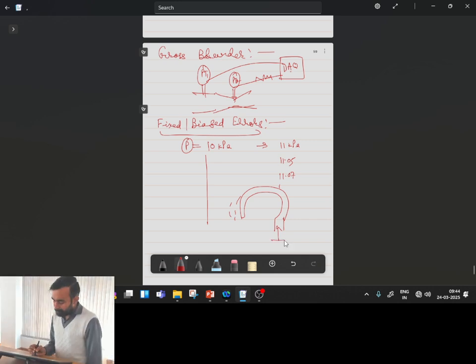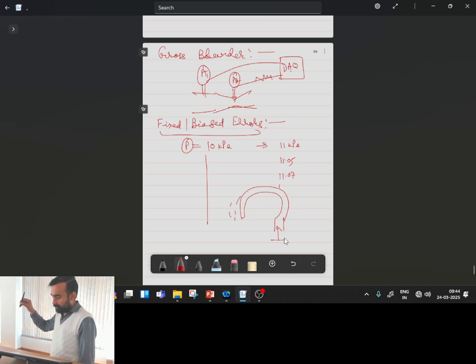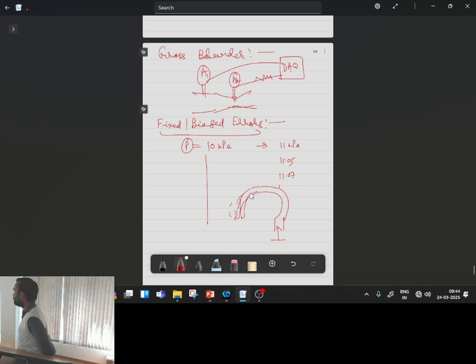If you keep this pressure gauge in long use, it will be subjected to multiple cycles of deflection and returning its shape to the original situation. Through repeated use, it may happen that after some time, instead of this shape, it has already obtained some deflected shape because of deformation of the material from its longer use.